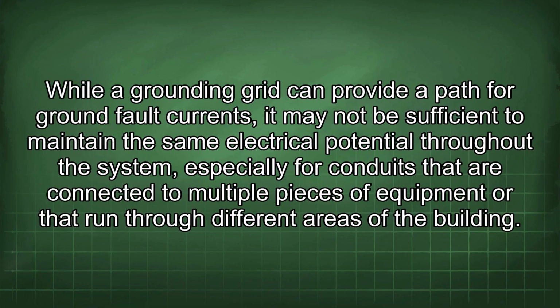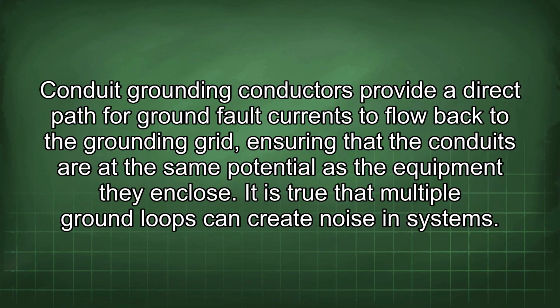While a grounding grid can provide a path for ground fault currents, it may not be sufficient to maintain the same electrical potential throughout the system, especially for conduits that are connected to multiple pieces of equipment or that run through different areas of the building. Conduit grounding conductors provide a direct path for ground fault currents to flow back to the grounding grid, ensuring that the conduits are at the same potential as the equipment they enclose.